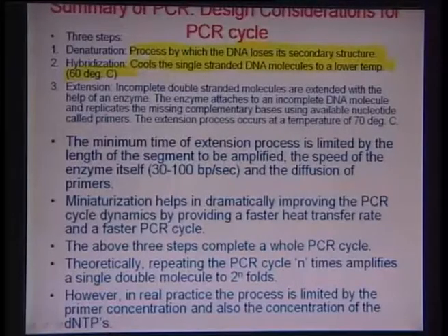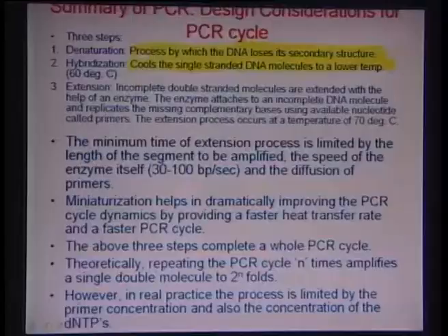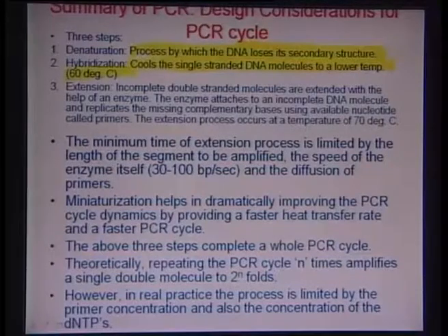And this essentially can be achieved in a thermal cycler, which is conventionally designed in a manner where there is a huge aluminum block with various through holes, and essentially this is used as a thermal cycling modality for holding together some vials with the PCR fluid in it. And then what happens is that the block is cycled at different temperature points by using a Peltier cooler and a resistance heater.